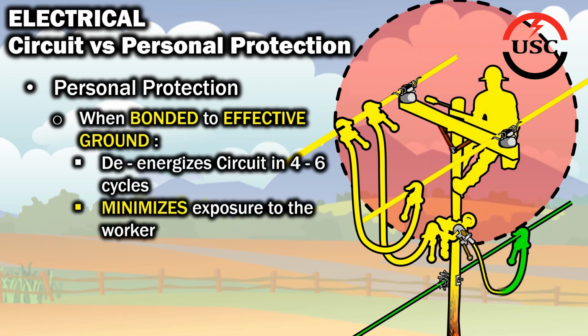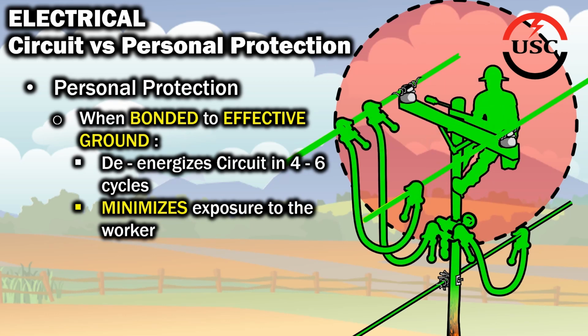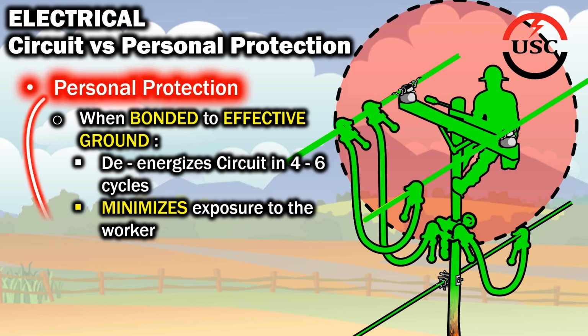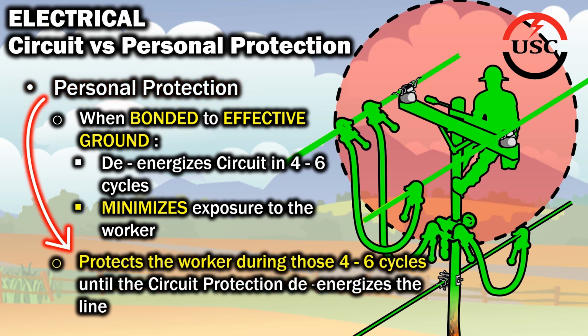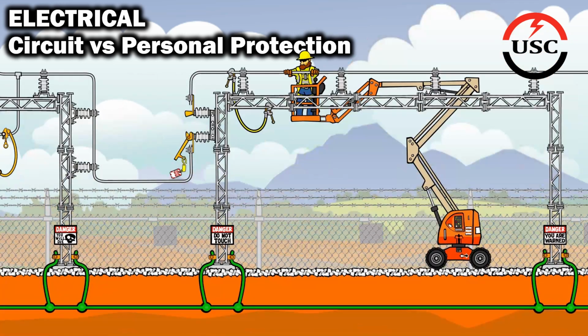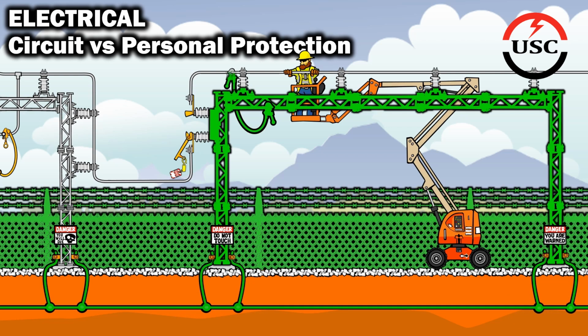Bonding the personal protection to an effective ground incorporates circuit protection. This is intended to de-energize the circuit in 4 to 6 cycles. Personal protection is designed to keep that worker safe during those 4 to 6 cycles. Here we've got a worker in a man basket inside of a substation. The buswork is bonded to the structural steel. The structural steel is bonded to an effective ground, which is the ground grid. Therefore, the buswork is considered grounded as well. This is your circuit protection.